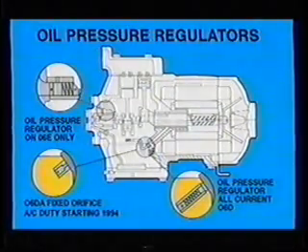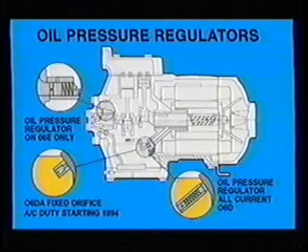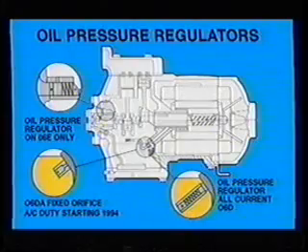On all OEM production O6D compressors, a new style regulator is positioned below the oil level, so the oil can't be pumped out through the equalization line when units are in parallel. Notice that the oil regulator on O6E compressors is on the pump end bearing head assembly.